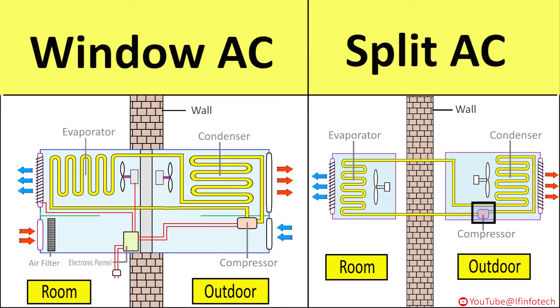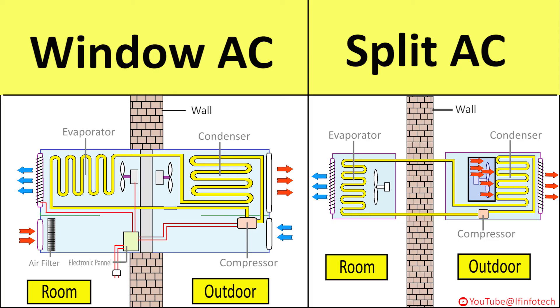The compressor inside the outdoor unit is controlled by a thermostat that detects warm air and activates the compressor. The compressor circulates refrigerant gas, increasing its pressure and temperature, then discharges it to the condenser. The condenser removes heat from the refrigerant and the gas changes phase to liquid. This chilled liquid refrigerant is forced through tubing indoors until it reaches the evaporator system.